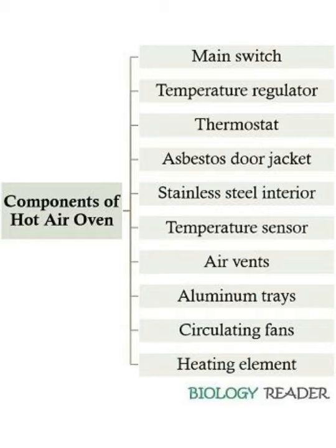The aluminum trays. The trays are generally perforated to facilitate the equal distribution of heat to the articles that are kept inside. Circulating fans. They perform a central role in the uniform flow of heat inside the hot air oven, along with improved temperature distribution. Heating element. Electrical coils are placed at the bottom of the instrument, which allows the upward movement of heat.